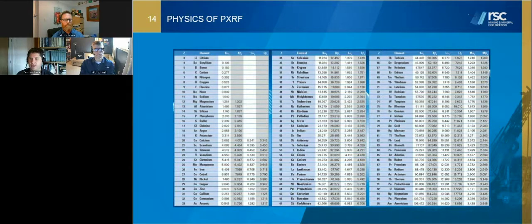We have tables of all the elemental interferences for the different elements. Sulfur, moly, and lead are all listed there, and this peak at about 2.3 keV is where that interference happens. You can work your way through the whole periodic table and find all the elements that interfere on each other. So there shouldn't really be any surprises when you ask whether the data for, say, gold is any good. You can find gold on this table and find that arsenic, tungsten, and zinc all interfere with it. So if you wanted to make a reliable method to quantify gold, you'd need to be thinking about how you dealt with those elements.